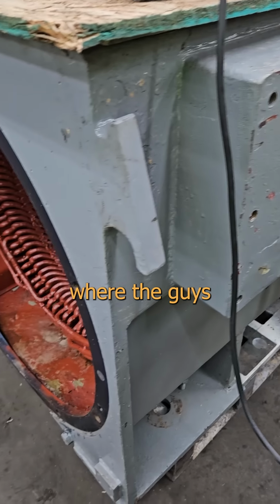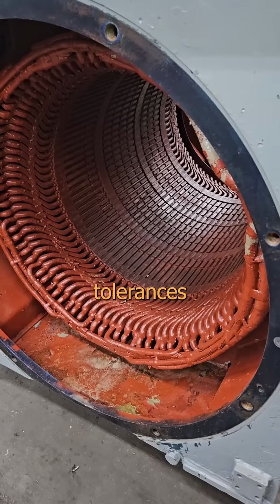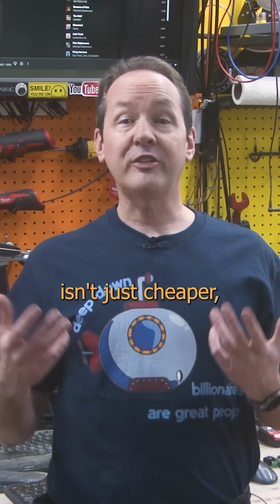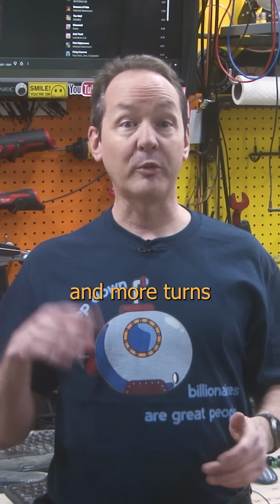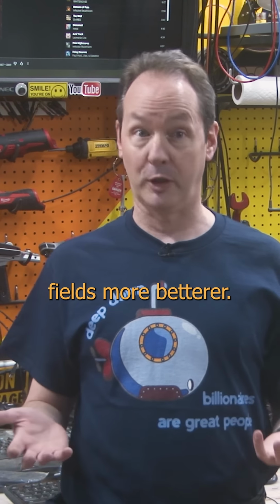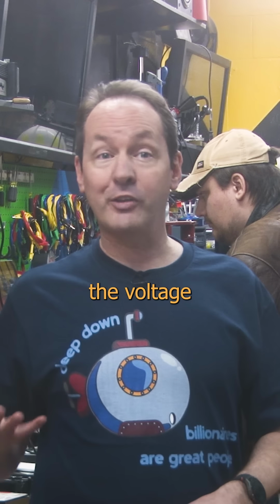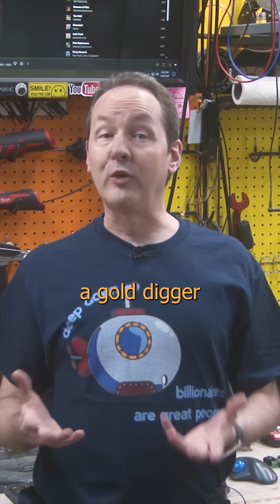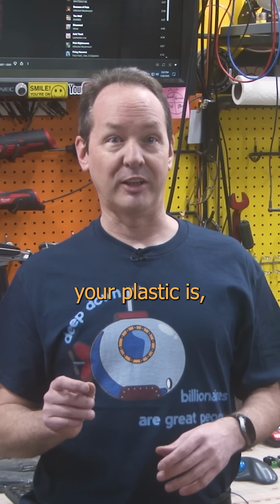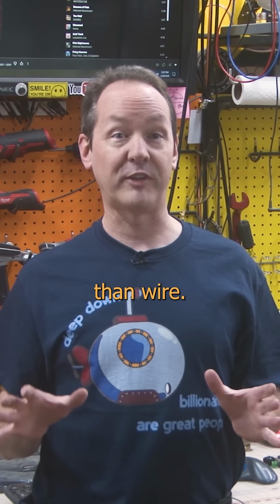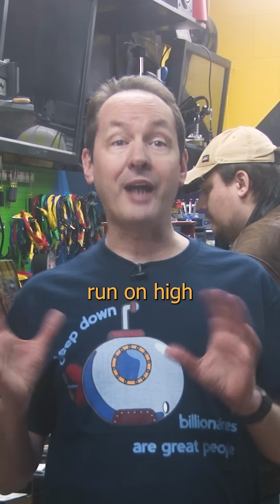Thankfully, this is a rare place where the guys that stack cash and the guys that stack tolerances actually agree. Because thin wire isn't just cheaper, it lets us have more turns in the coils, and more turns make magnetic fields better. So we can cut down the amps if we jack the voltage up high. Voltage is a gold digger and only cares about how thick your insulation is, but insulation is way less expensive than wire, and that's why big motors run on high voltage.